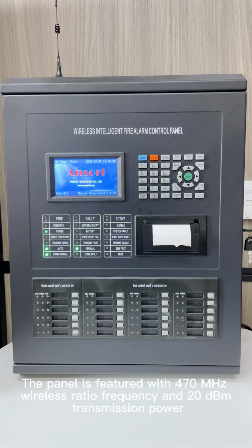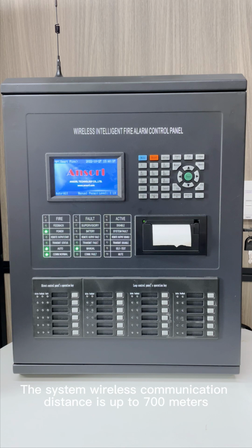The panel is featured with 470 MHz wireless radio frequency and 20 dBm transmission power. The system wireless communication distance is up to 700 meters, depending on the actual situations and plans. During installation, wireless signal extender can be added to enhance and expand signal.